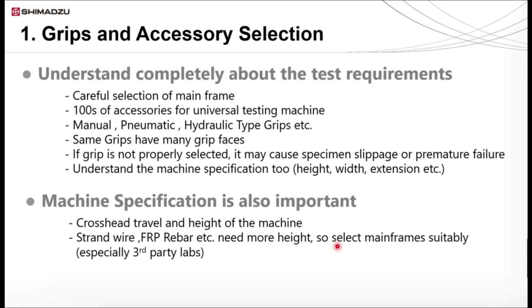Also, as I explained, understanding the machine specification is very important: height of the machine, width of the machine, crosshead travel, load cell class, extensometer class, etc. For samples like strand wire or FRP rebar, the gauge length requirement is very large. In such cases, an extended length frame is mandatory. Once the purchase is done, it will be very expensive to modify the machine.